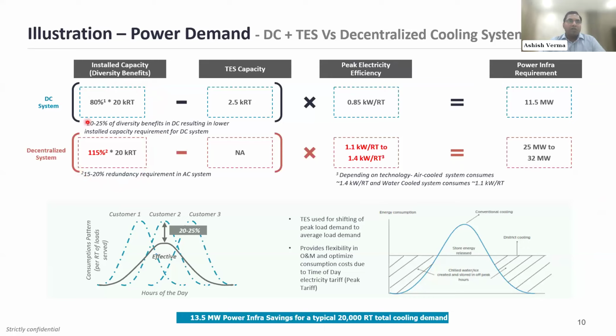When we go for a district cooling system, we definitely have the advantage of demand aggregation, and that gives us better diversity. We have assumed a diversity of 80% here. So instead of 20,000, to meet this cooling demand of 20,000 refrigeration tons, we can probably install a capacity of around 16,000 tons because of the diversity benefits. If we couple a thermal energy storage tank also, the capacity will be 2.5 KRT, that is 2,500 refrigeration tons. It helps in reducing, first of all, the mechanical capacity of the cooling plant, and your power consumption is only for the mechanical component and not for the thermal energy storage.